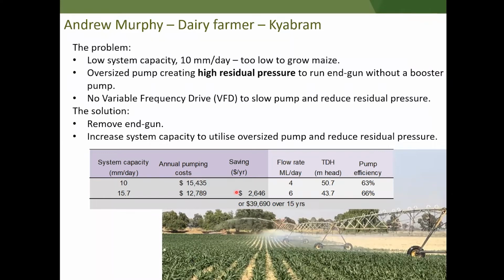Yeah, so overall, the estimates: the pumping costs went from using about 250 kilowatt hours per megalitre back to about 200, so about a 20% reduction in energy costs. Assuming growing maize under this system, it comes out at a saving of about $2,600 a year by reducing that total dynamic head. In this particular system, I think there's still opportunities because of that older pump. The pump efficiency is still not over that 70%. So I think there's still opportunities there to perhaps look at the impeller and look at how that pump's actually performing. But a fairly simple cost.